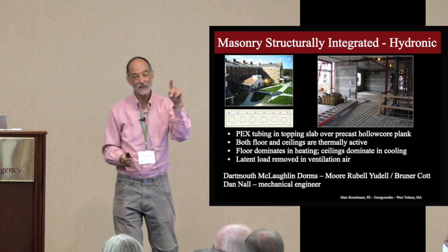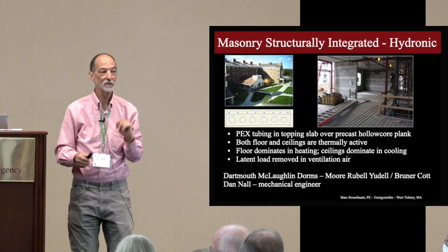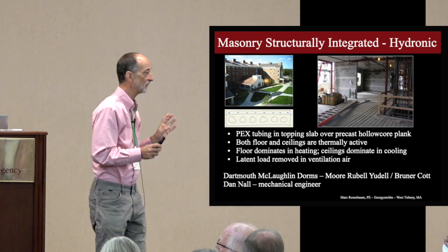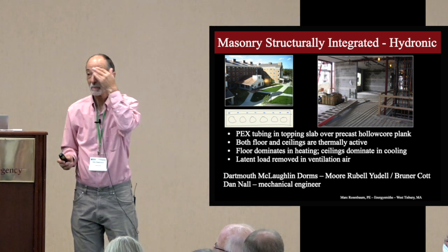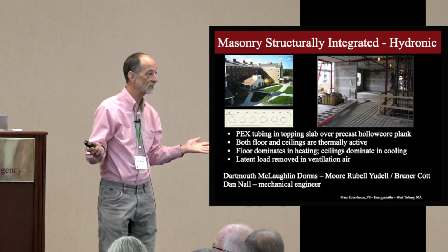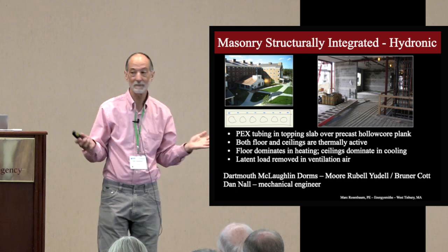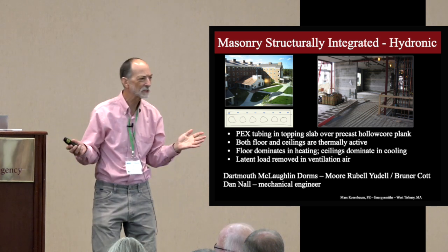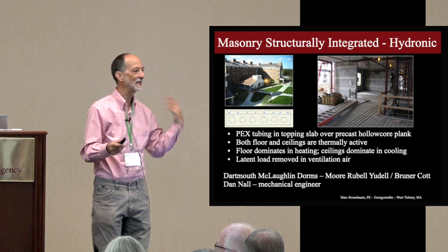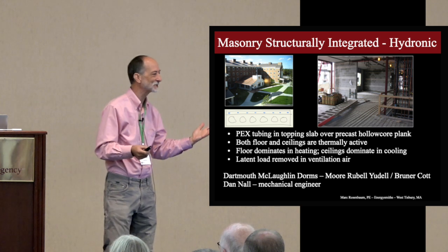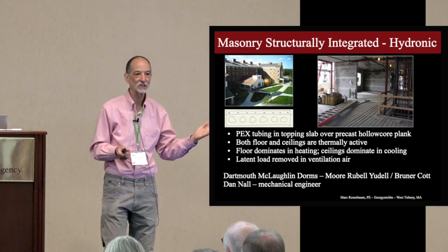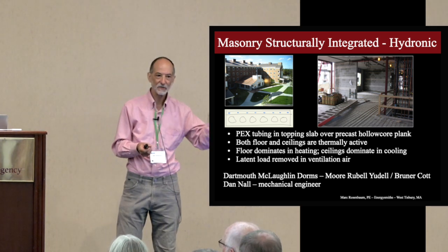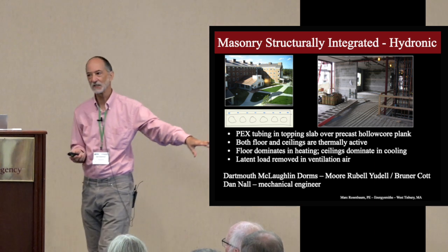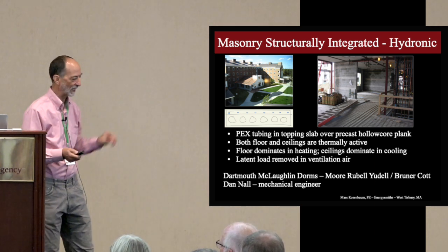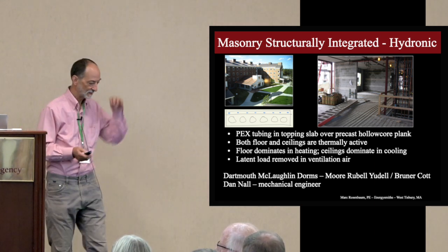And this is a key thing: the latent load is removed in the ventilation air. So the ventilation air is very dry, but you need a lot of it for such a densely occupied building like a college dorm. You wouldn't do this in a house, you can't dehumidify a house with 100 CFM of ventilation air. But here, every dorm room gets a certain amount of ventilation air, a lot of air is moving around, and all the latent load comes out through that ventilation air.